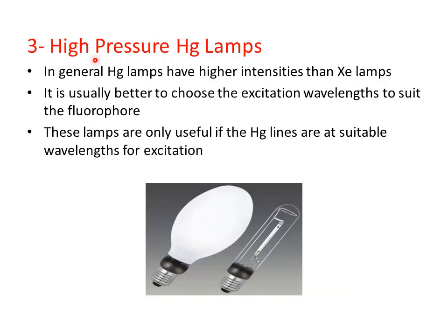Another light source is the high pressure mercury lamp. In general, mercury lamps have higher intensities than xenon lamps, and it is usually better to choose excitation wavelengths to suit the fluorophore. These lamps are only useful if the mercury emission lines are at suitable wavelengths for excitation, meaning their energy matches what is required to excite the atom from the ground state to the excited state.